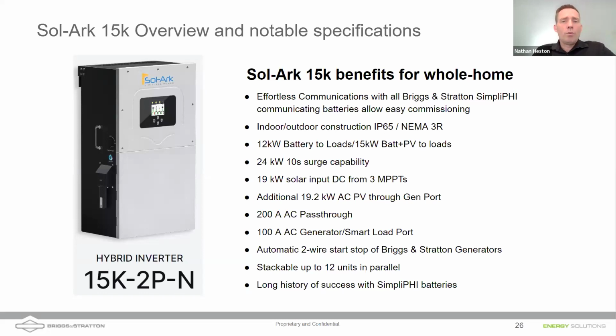You can do 12 kilowatts battery to loads, and 15 kilowatts of power when you've got PV available together with batteries. You can surge for, I thought it was 5 seconds, I guess it's 10 seconds, at 24 kilowatts of power, so it's a lot of power to start up those larger loads. You can bring in 19 kilowatts of solar from the DC side and an additional 19.2 kilowatts of AC through the Gen port or the Smart Loads port. It's got 200 amp pass-through.